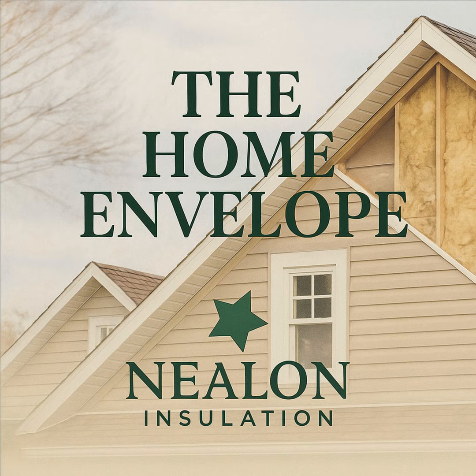90%? That's huge. It is, but they require very specific installation conditions. Right. The papers mention they need a dedicated air gap. Yes. They must have an open air space facing the reflective side to function. You can't sandwich a radiant barrier between two solid materials, or it just becomes a thermal conductor. That makes sense. Additionally, if that foil gets covered in a layer of attic dust over the years, it loses its reflectivity and becomes practically useless. So maintenance is key there.